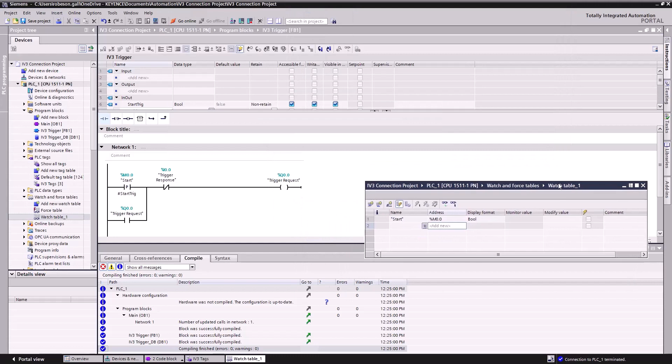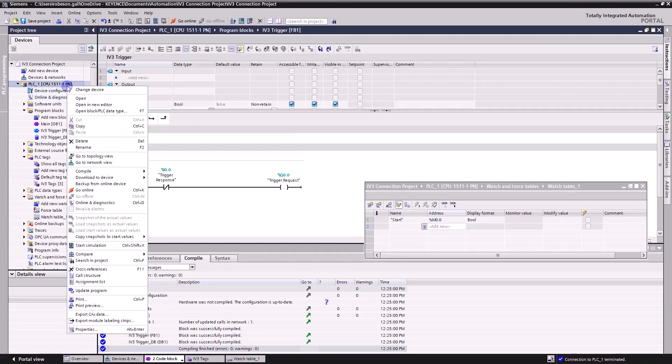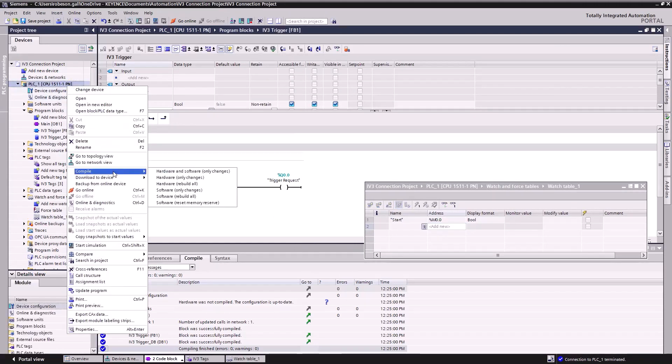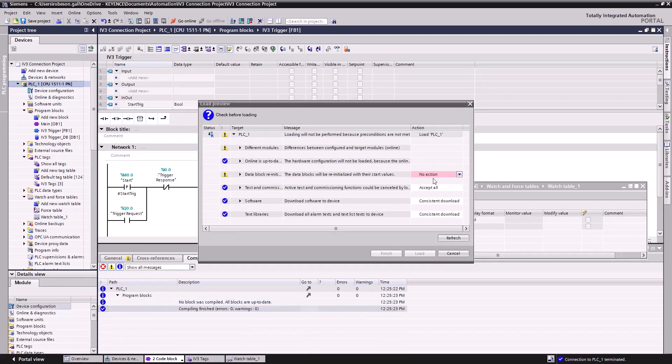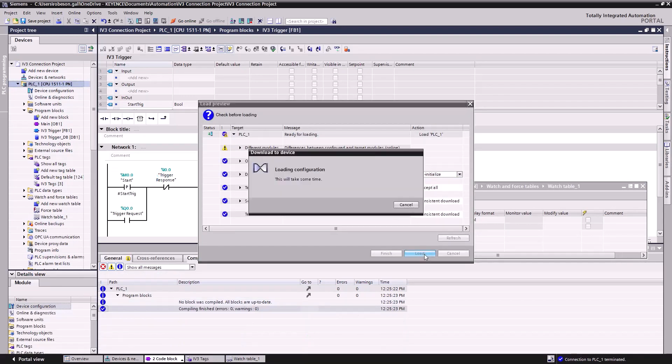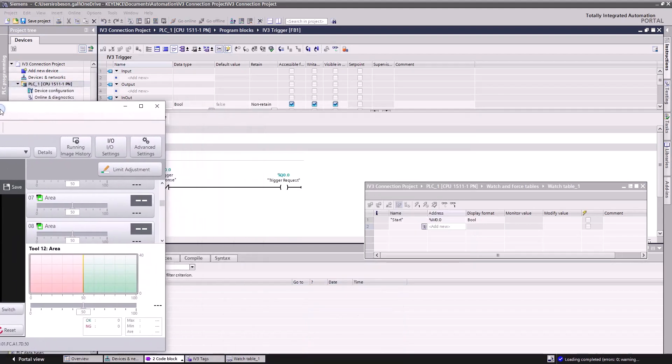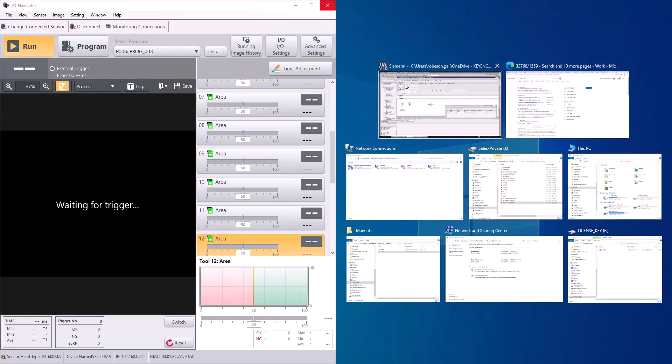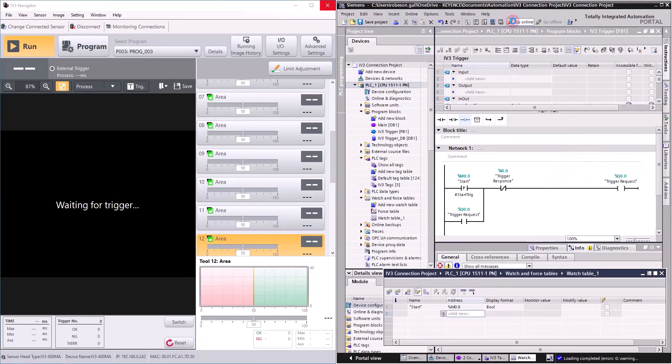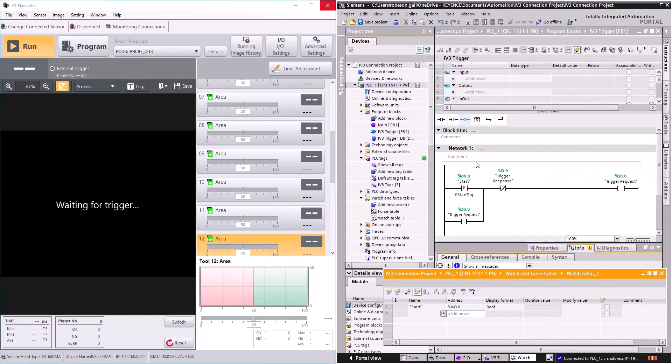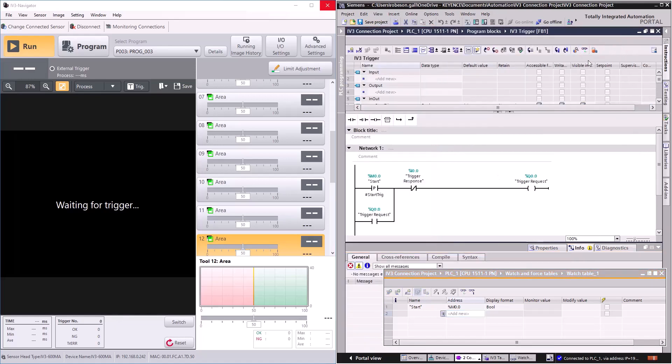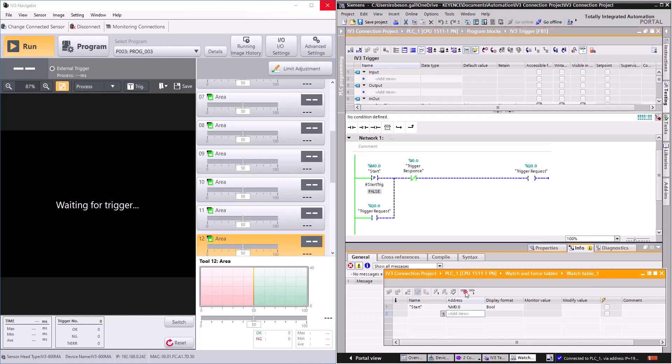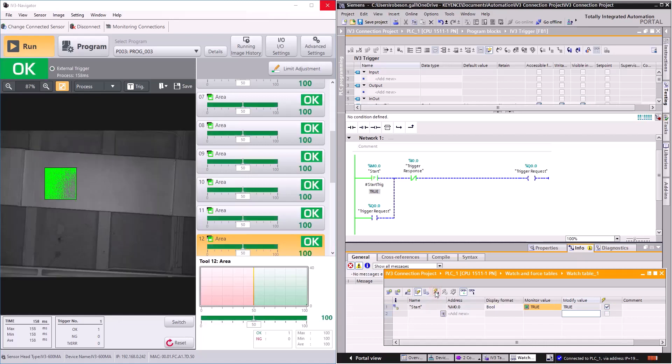Now I'll right-click the PLC again, this time selecting Download Hardware and Software Only Changes. This process will take a bit of time. Once that's complete, I'll drag in our IV-3 Navigator window to show the effect. Click Go Online to start communication with the PLC. I'll click the Glasses icon so we can watch the logic change live. I'll also click the Glasses icon in our Watch Table so we can monitor the bit. Now I'll change my Modify value to 1 or True. Now I can click the Lightning icon to modify the value and you'll see this triggers our IV-3. Thanks for watching.